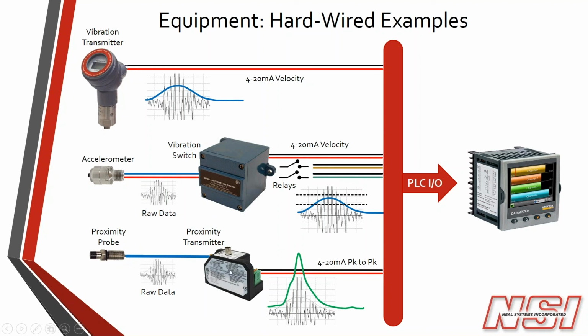But here we can take this transmitter and the raw data coming out of the probe and analyze it, calculate the peak-to-peak displacement, and convert that into a 4 to 20 signal as well. So all of these outputs can be brought to a typical PLC and trended. Or you can run logic on those without any specialized equipment between the instruments and the PLC.